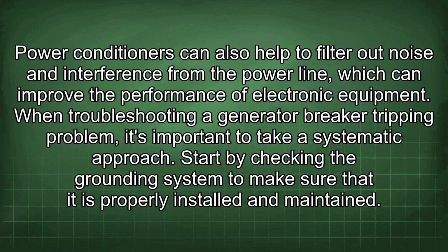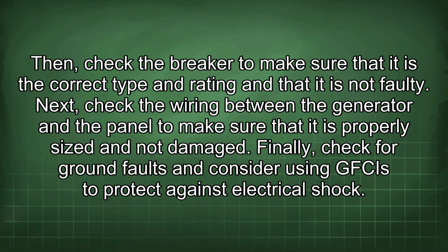When troubleshooting a generator breaker tripping problem, it's important to take a systematic approach. Start by checking the grounding system to make sure that it is properly installed and maintained. Then check the breaker to make sure that it is the correct type and rating and that it is not faulty. Next, check the wiring between the generator and the panel to make sure that it is properly sized and not damaged. Finally, check for ground faults and consider using GFCIs to protect against electrical shock.